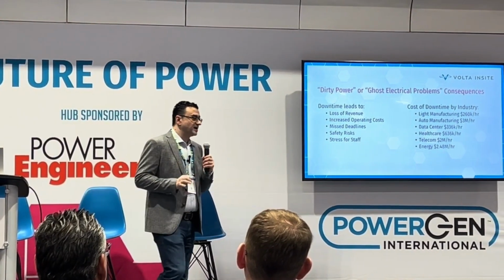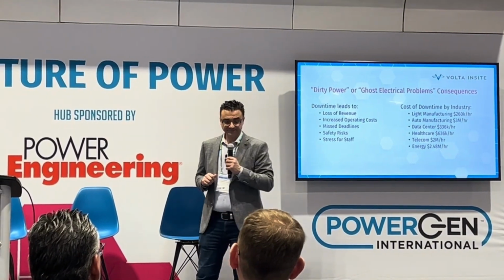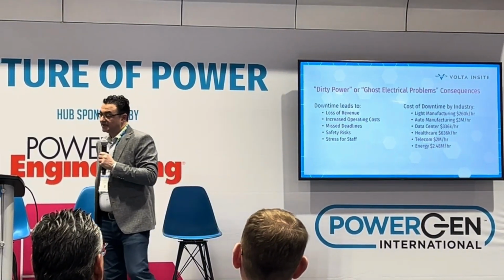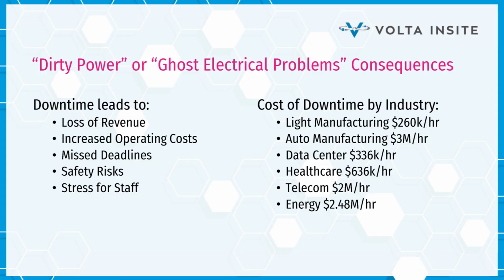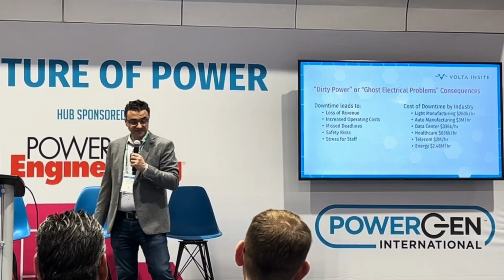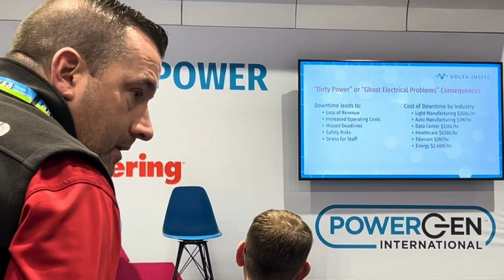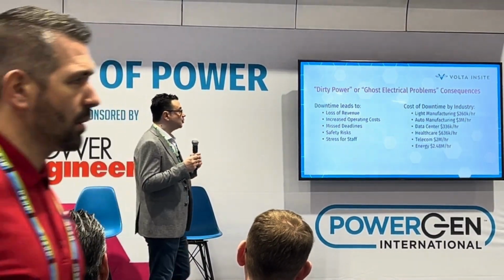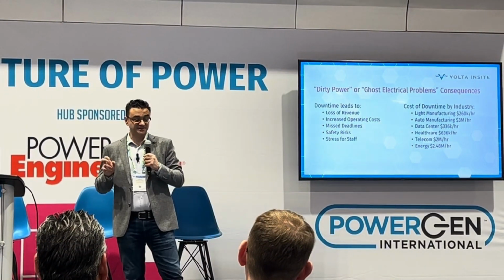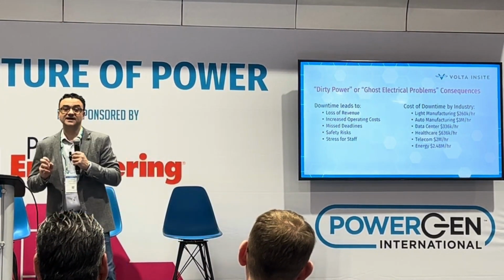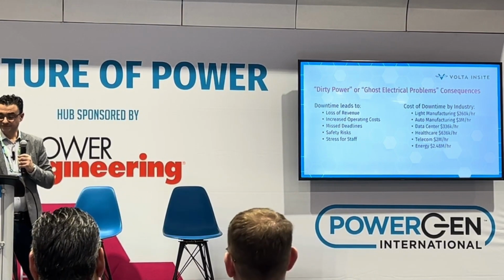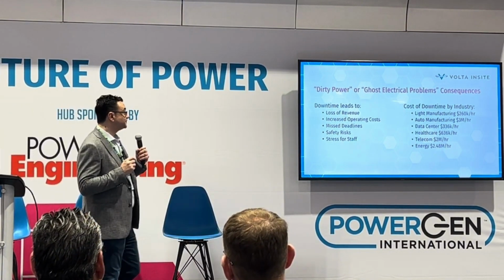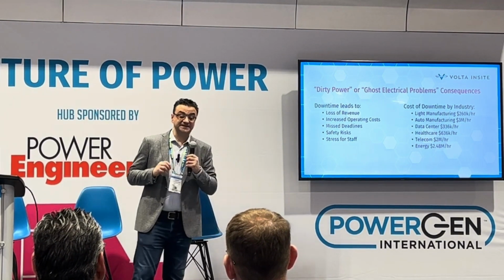Why is dirty power, or a lack of good power quality, a problem? It leads to loss of revenue within your facility. It increases operating costs. If you're in a production facility and you have specific timelines about delivering product, you can miss deadlines. There are safety risks, obviously, and it's additional headaches for staff. A lot of power quality issues are also called, within the technician world, ghost electrical problems because they can't be diagnosed.